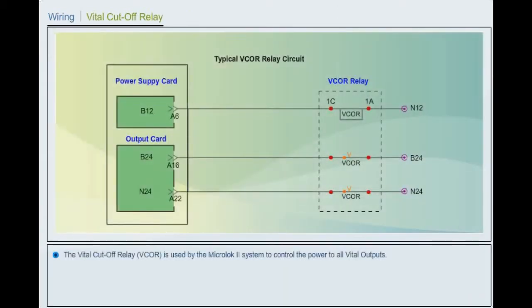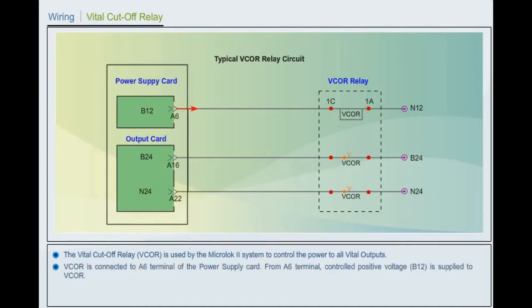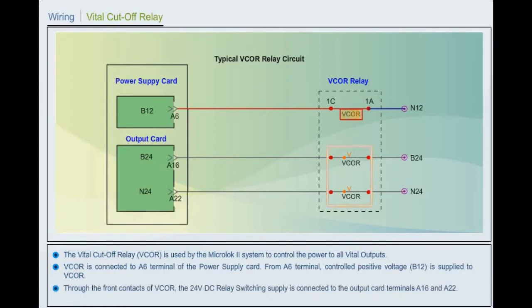Wiring. Vital cutoff relay. The vital cutoff relay, VCOR, is used by the Microlok II system to control the power to all vital outputs. Vital cutoff relay is connected to A6 terminal of the power supply card. From A6 terminal, controlled positive voltage B12 is supplied to VCOR. Through the front contacts of VCOR, the 24 volts DC relay switching supply is connected to the output card terminals A16 and A22.